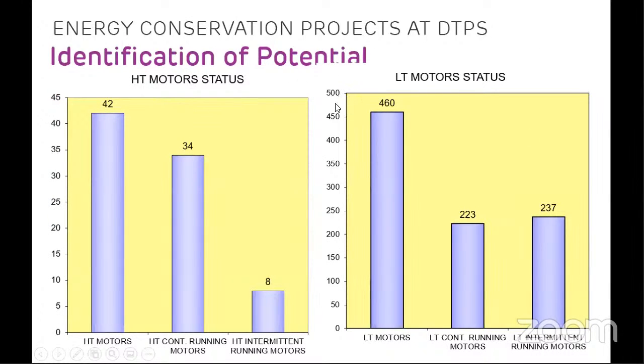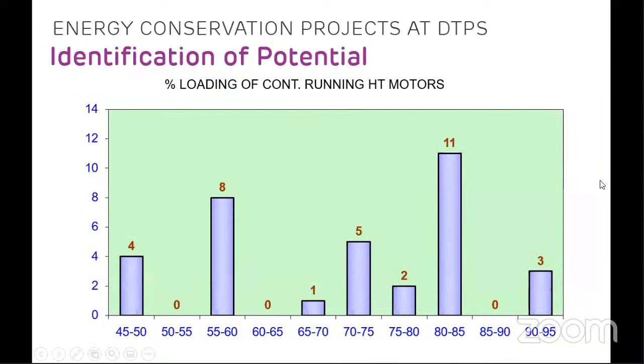Then, going further with our survey, we carried out a survey of individual HT motors. There are 42 HT motors. Out of these, 34 HT motors are continuous running and 8 motors are intermittent running. Now, if a motor is running intermittently for short periods, then there is no point in installing a variable frequency drive on that motor because the savings will not be significant. So we identified these 34 motors and continued our survey. Similarly, for LT motors, out of 460, 223 were continuous running and 237 were intermittent. So we focused on these 223 continuous running motors. Now we further broke down this data and found out the loading of each motor.